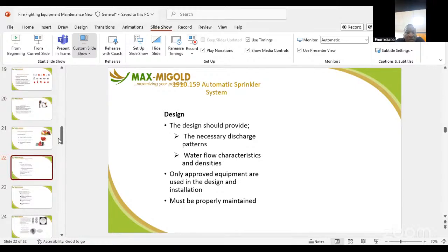We're also saying that for automatic sprinkler systems, we look at OSHA 1910.159, as well as NFPA 13. If you look at the necessary discharge pattern, we should look at the water flow characteristics and density. Where is the water coming from? At what pressure? What is the pump pushing it? Of course, it's going to be a closed design system, but we need to know the size of the piping. That will help us determine the force per area that is being pushed along that sprinkler head. And again, the use of the space will tell us what we should do in terms of the sprinkler system. Federally approved equipment is used as per design, and maintenance is king, not key. Maintenance is king, so we should ensure that maintenance happens as and when due. Next slide, please.